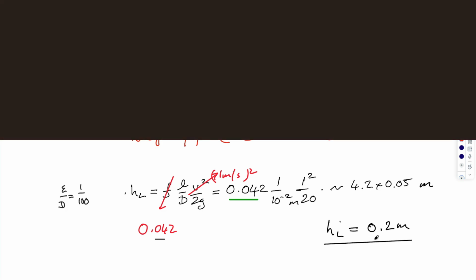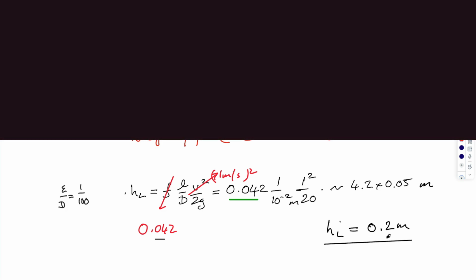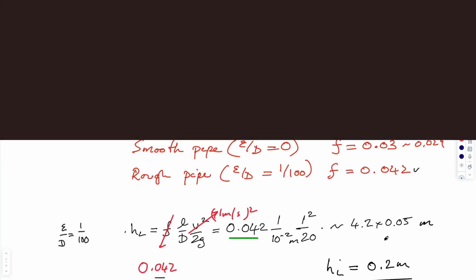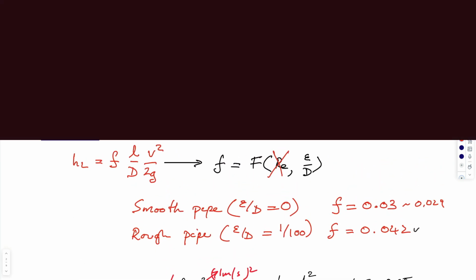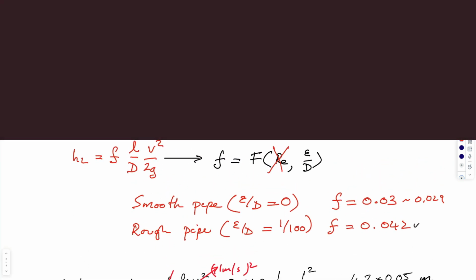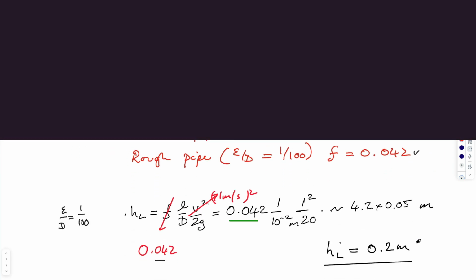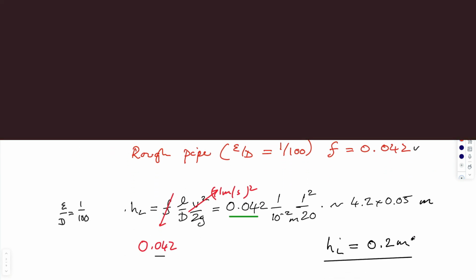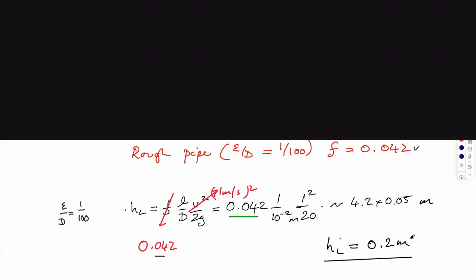It comes out to be a head loss of 0.2 of a meter. So before it was 3 millimeters, now 0.2 of a meter is 200 millimeters. So the head loss is much bigger to get a bigger velocity through the system. The head loss was a small number before, now it's much larger because we're trying to push it through 10 times faster in essentially the same pipe.